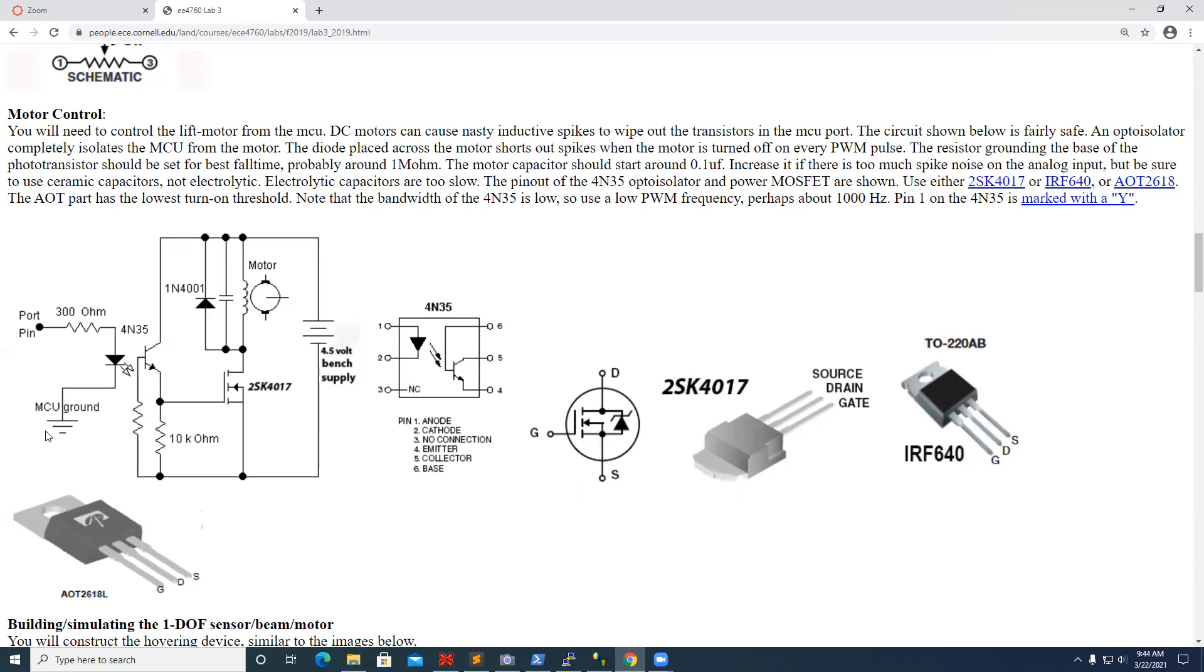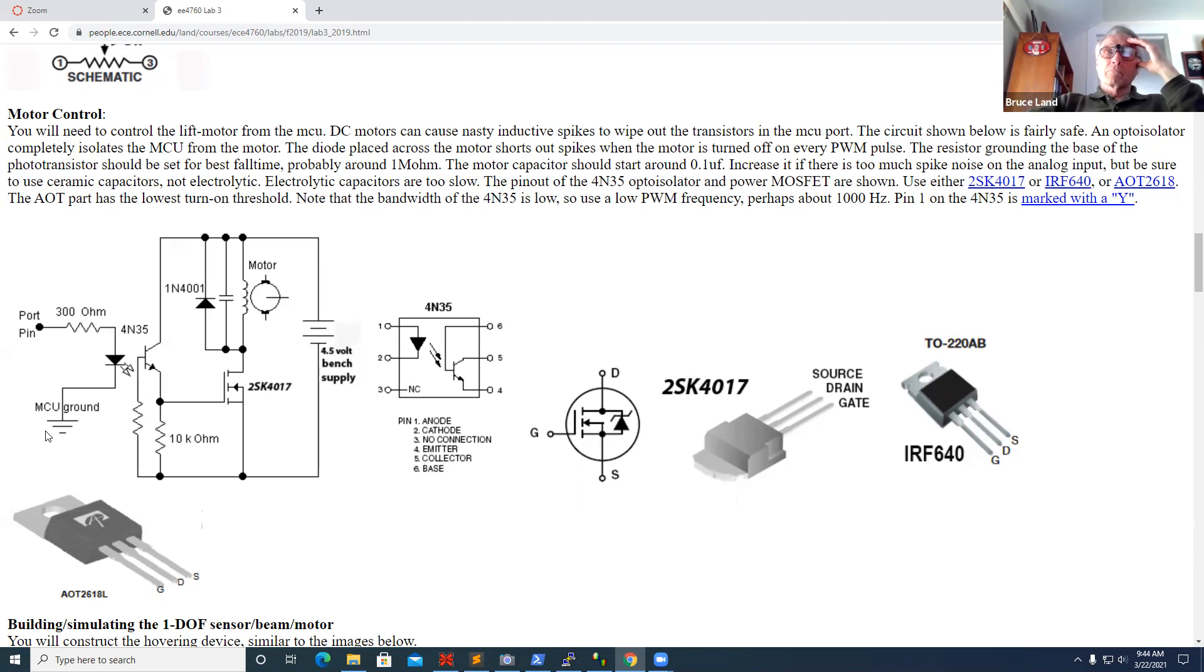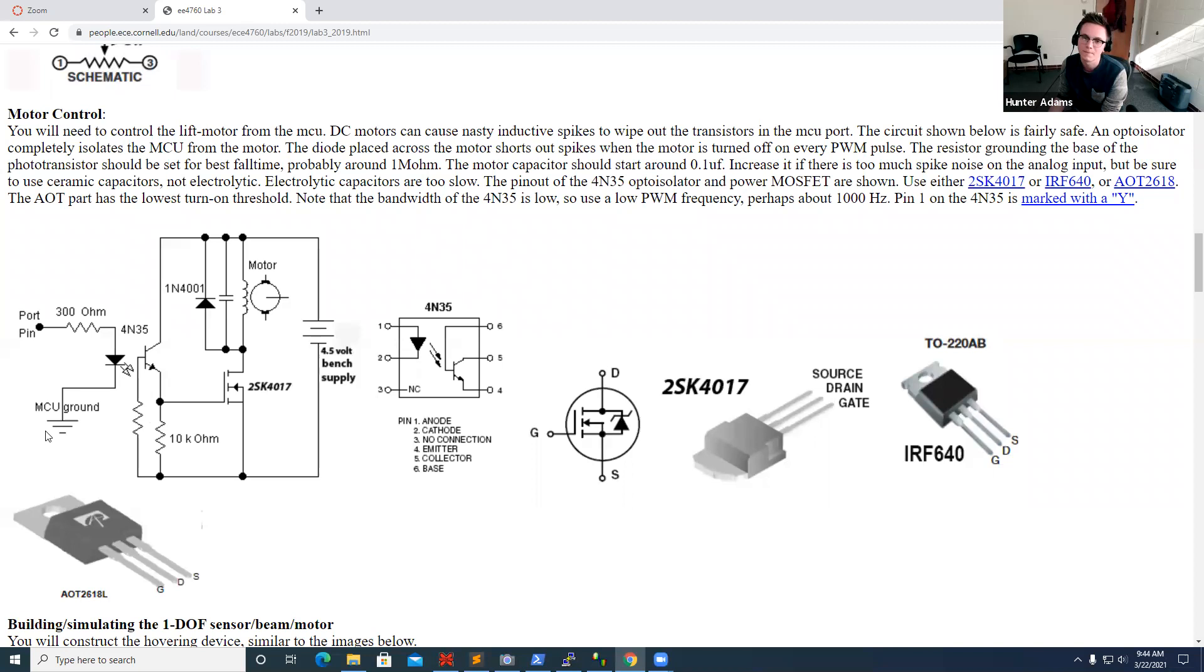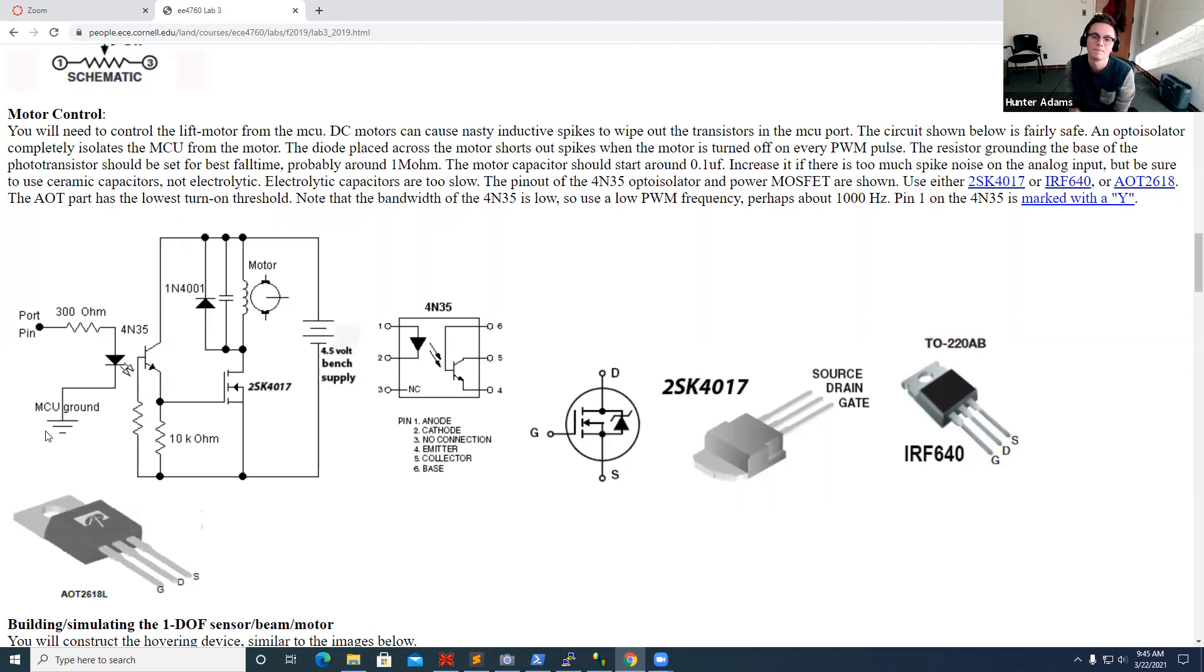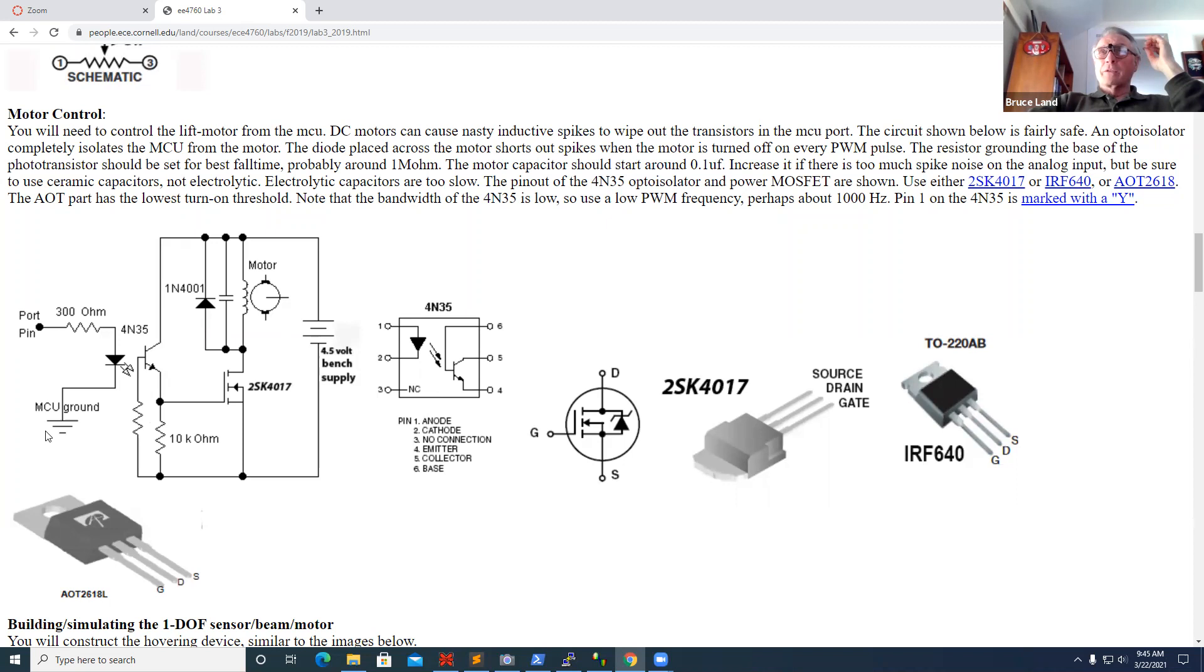This almost entirely incidentally, but just because it's kind of interesting, this notion of electrical isolation is also super important in any sort of biomedical application. So you look at things where you are outfitting human bodies with electronics to protect the people wearing or perhaps having those electronics put in their bodies, depending on the application. Electrical isolation is wildly important for safety. As little as 30 microamps in a heart catheter, 30 microamp flow of AC flow, 60 hertz flow out of a heart catheter will kill a person. And so getting the leakage current down below a microamp is hard. All we do is isolation.